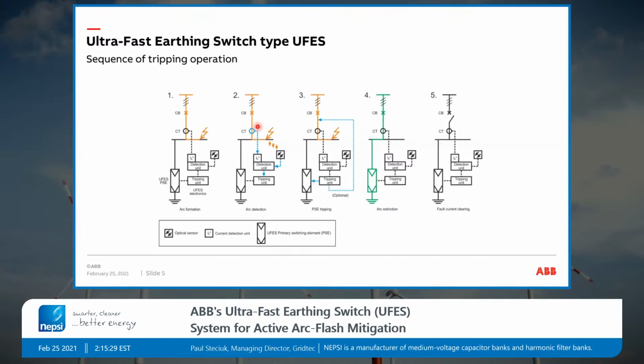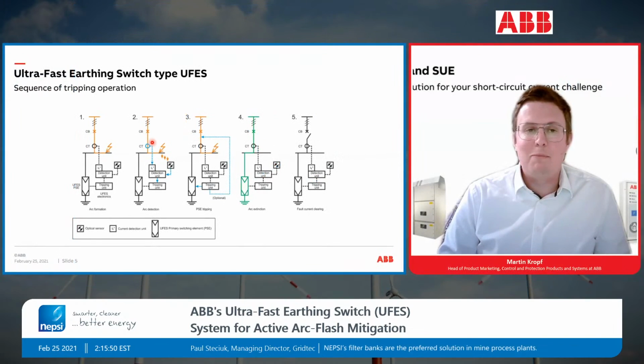Since only light, we can do that as well. We can do light or current. It's also possible, or only current or only light. Both are possible, but we recommend the logical AND. Why? Because if we have only light, we have the risk that maybe at the commissioning of the switchboard, the customer is happy about it. He would like to make a picture. He uses a bit of strong flash, and then we have the trip, because a strong flash of a camera can really trip also the light sensors.